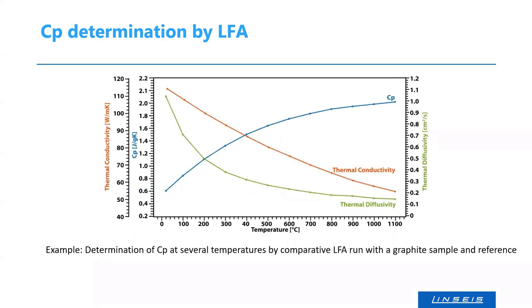If you find a fitting reference — for example, a graphite sample measured with a graphite reference — you can determine CP at several temperature steps, obtain the CP curve, and then calculate the thermal conductivity curve from the LFA data.